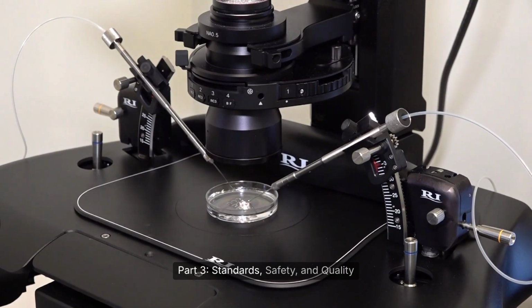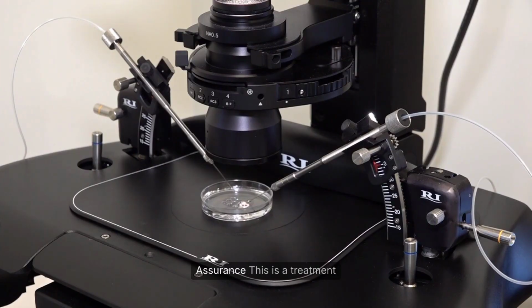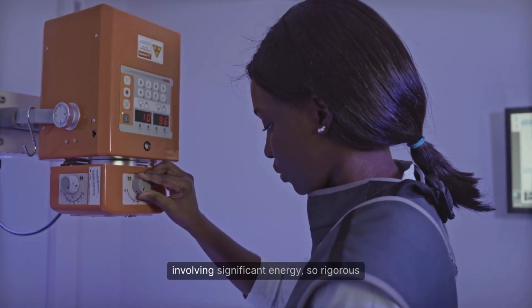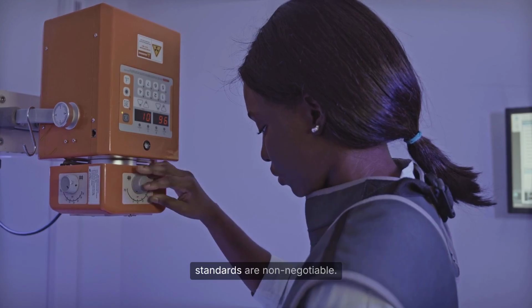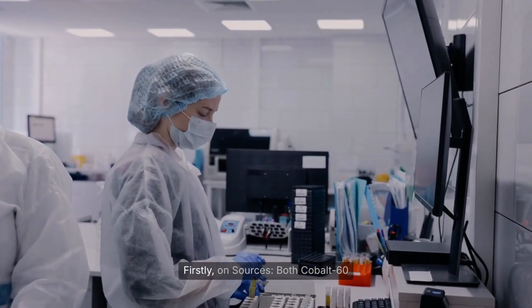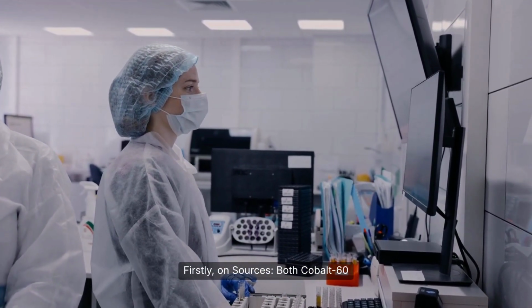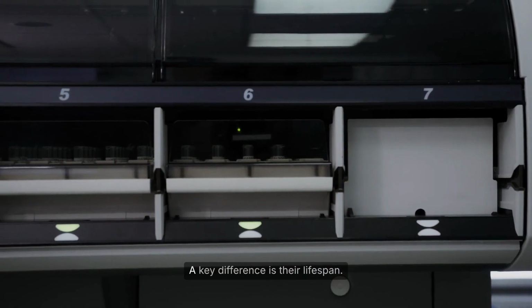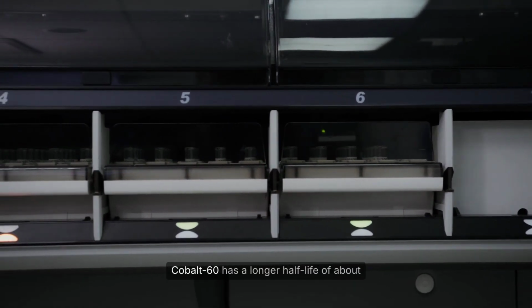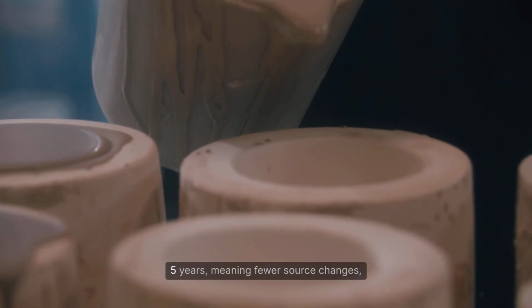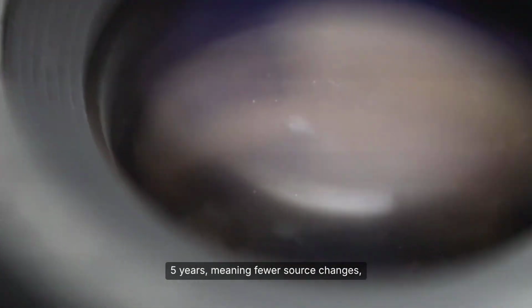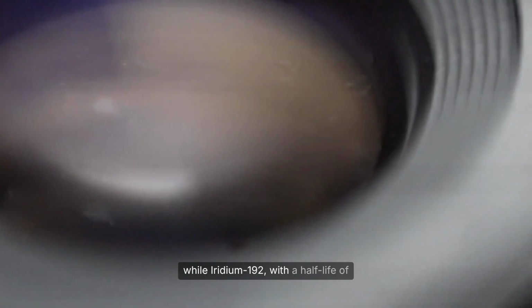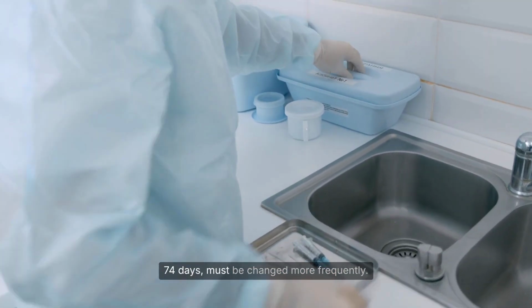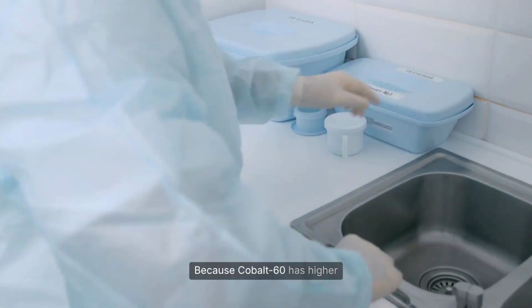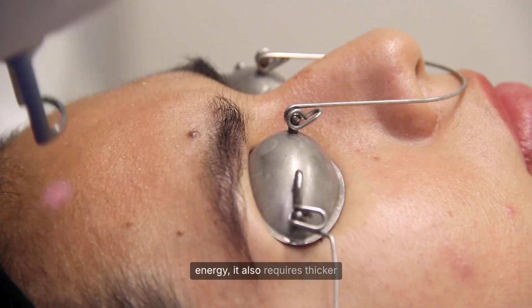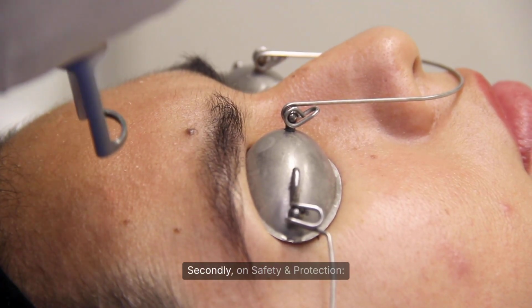Part 3. Standards, safety, and quality assurance. This is a treatment involving significant energy, so rigorous standards are non-negotiable. Firstly, on sources, both cobalt-60 and iridium-192 are used. A key difference is their lifespan. Cobalt-60 has a longer half-life of about 5 years, meaning fewer source changes, while iridium-192, with a half-life of 74 days, must be changed more frequently. Because cobalt-60 has higher energy, it also requires thicker shielding in the treatment room.